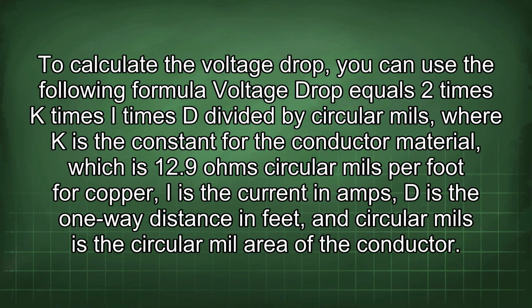To calculate the voltage drop, you can use the following formula: voltage drop equals 2 times K times I times D divided by circular mils, where K is the constant for the conductor material, which is 12.9 ohm-circular mils per foot for copper.